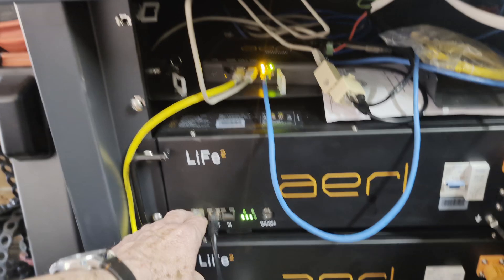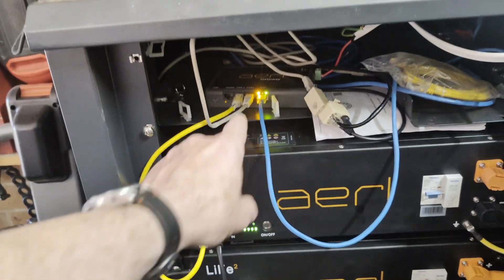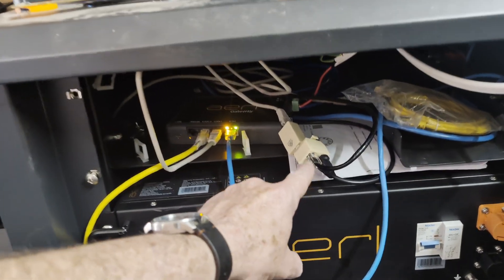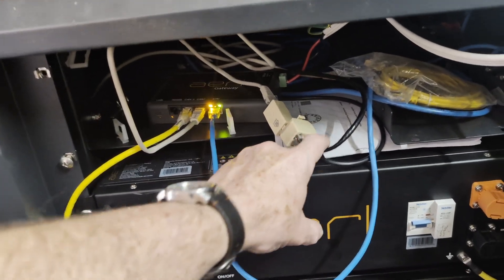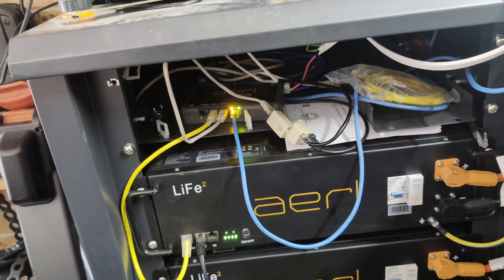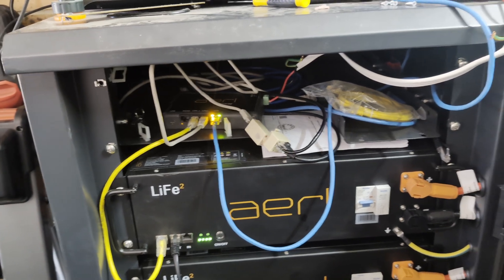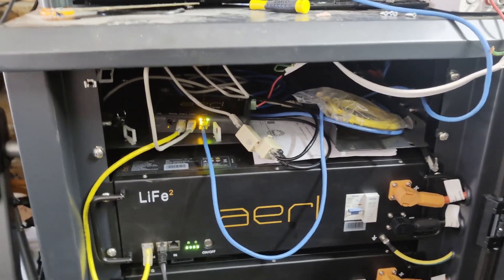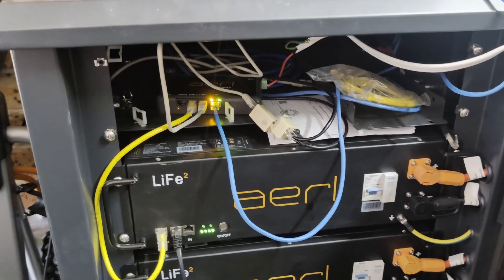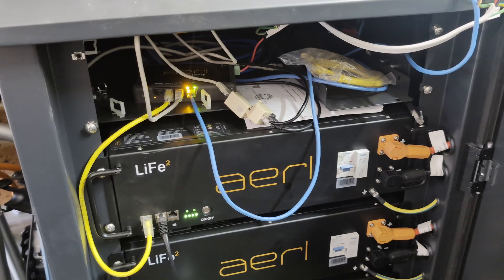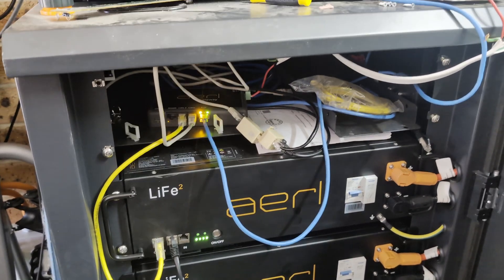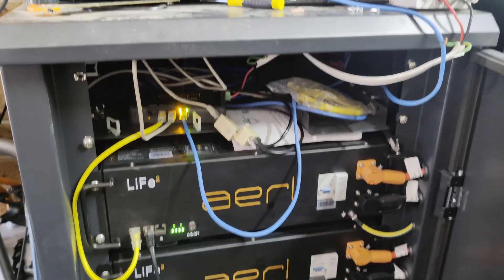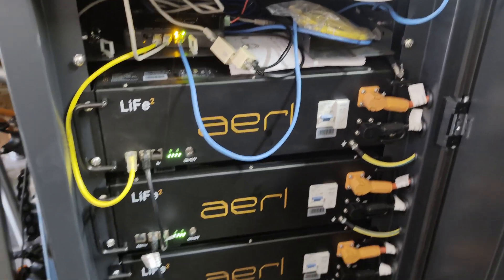it didn't work on the output side of the gateway because the internal pins, just two pins there for the RS-485, weren't actually joined through because that's a specific DI thing, not an industry standard thing. Anyway, they're back up and running now. Woo-hoo!